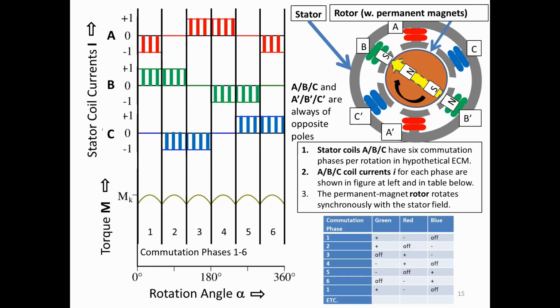And this is a very elegant arrangement because you can change the speed easily just by increasing or decreasing the size of the steps between these pulses. And what I've shown here is the hypothetical voltages in the 3 coils as a function of time across the course of one complete rotation. From here to here, the rotor rotates 360 degrees. During that time, red shows the currents in the red pair of coils. You have a positive pole and a negative pole. Green in the green pair of coils, and blue in the blue pair of coils.